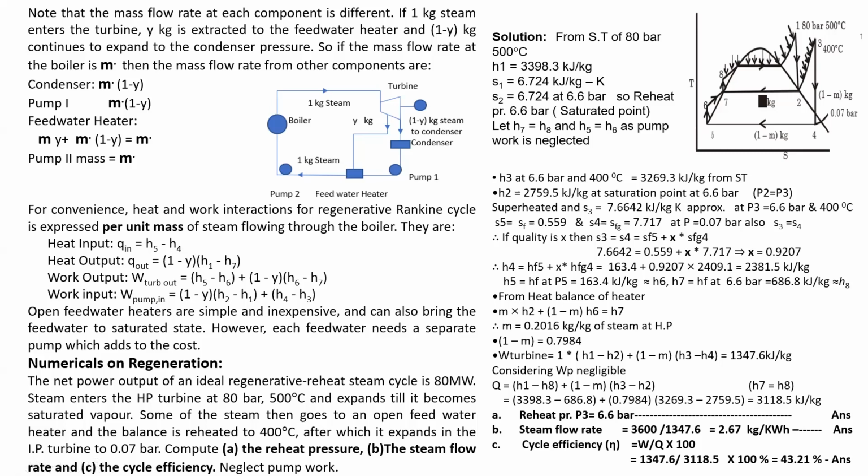Open feed water heaters are simple and inexpensive and can also bring the feed water to the saturated state. However, each feed water heater needs a separate pump, which adds to the cost.